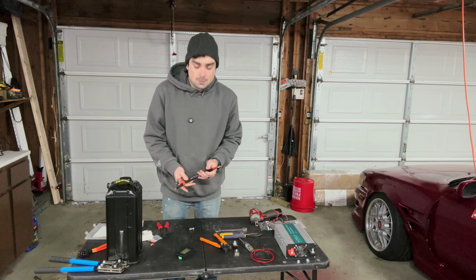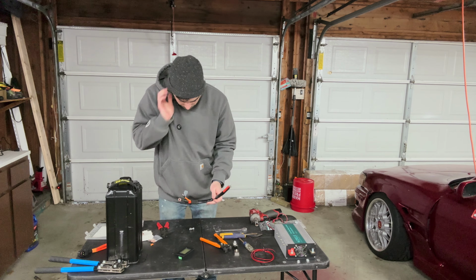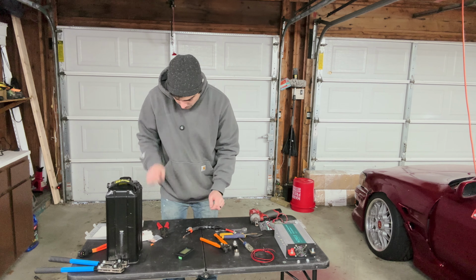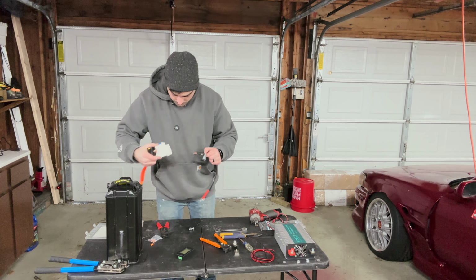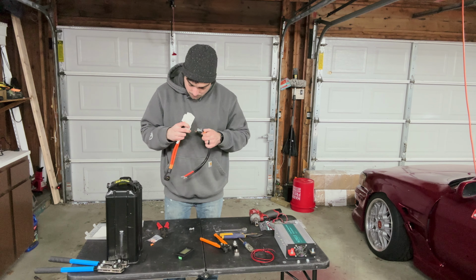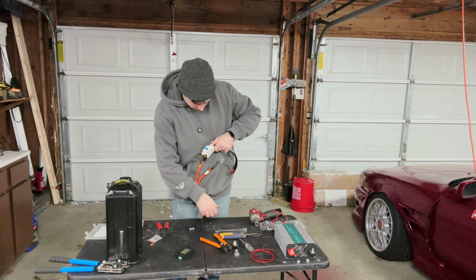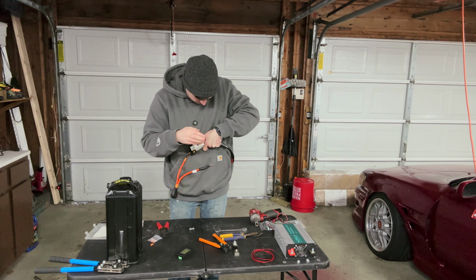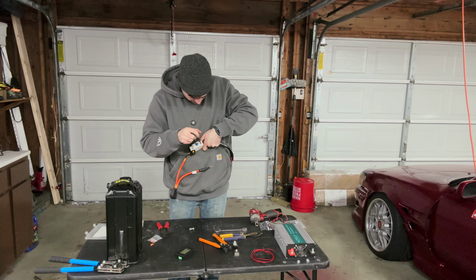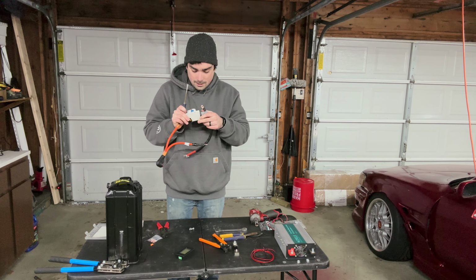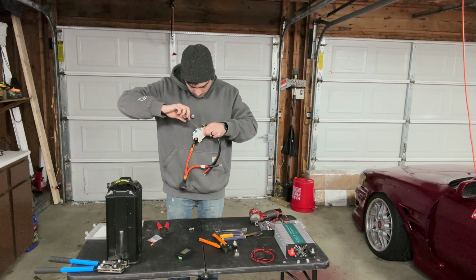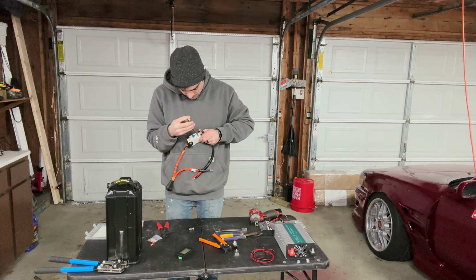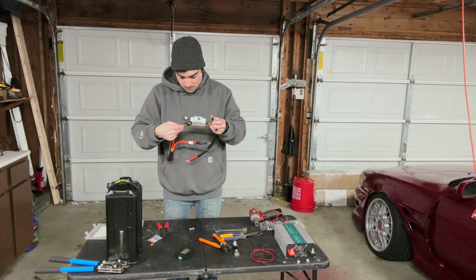Now that we have the two sides of this harness ready, we're going to put them together. The easier step is to put this one into the circuit breaker. So we put it in the slot, grab my screwdriver, and tighten it down. You want to make sure you're actually screwing down to the metal part — if you're screwing down to the heat shrink or the insulation, it's not going to make a good contact. So you got to make sure that's correct.